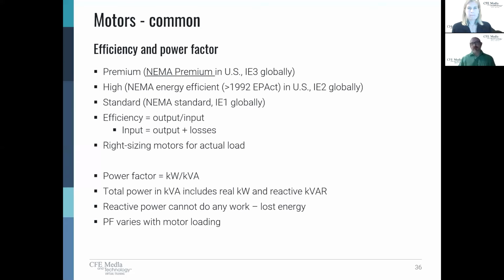And engineers should understand that sometimes a smaller motor is going to be more efficient in some aspects and less efficient in others. From a power factor standpoint, it's a pretty old idea. Obviously, it's been around for a long time. We understand that there's real power and imaginary power, and that we call that reactive or kVAR. And the main understanding that engineers should have is that if you have a very lagging power factor, for example, you're going to have a lot more reactive power that's essentially not doing any work. And utilities can commonly charge higher rates if you have a very substantially lagging power factor.